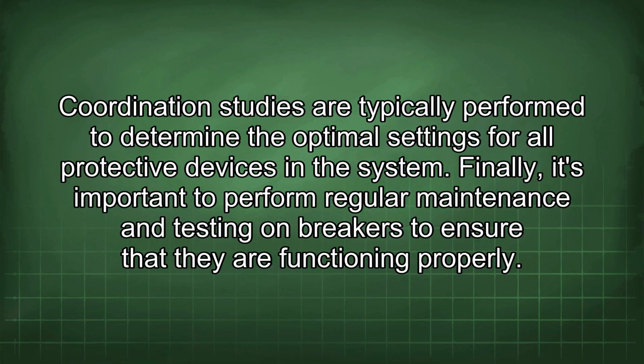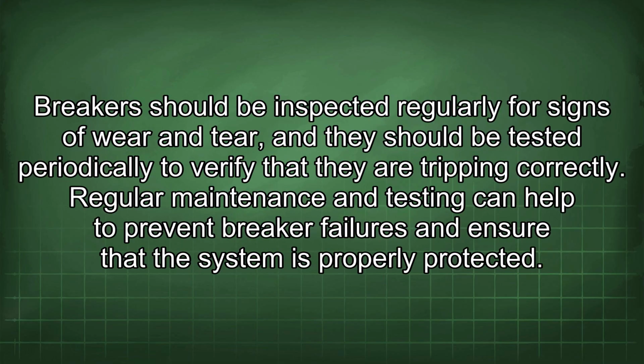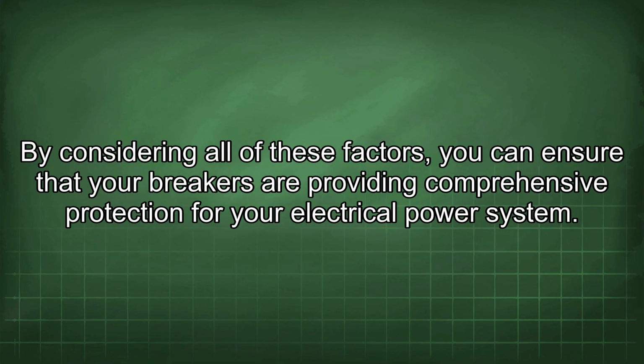Finally, it's important to perform regular maintenance and testing on breakers to ensure that they are functioning properly. Breakers should be inspected regularly for signs of wear and tear, and they should be tested periodically to verify that they are tripping correctly. Regular maintenance and testing can help to prevent breaker failures and ensure that the system is properly protected. By considering all of these factors, you can ensure that your breakers are providing comprehensive protection for your electrical power system.